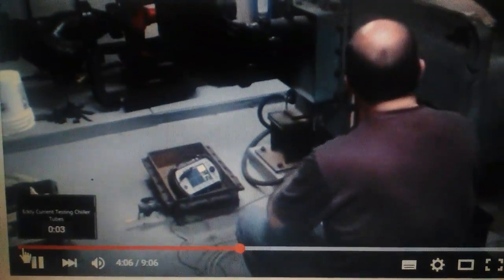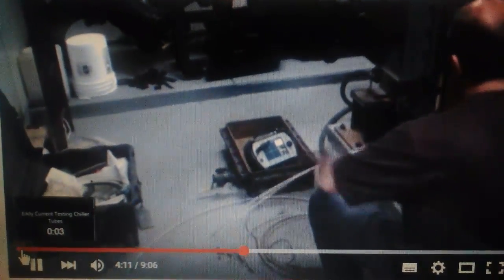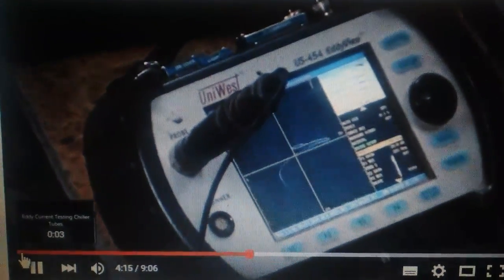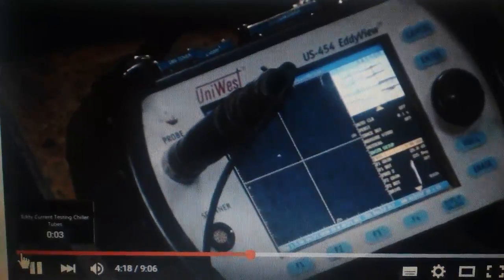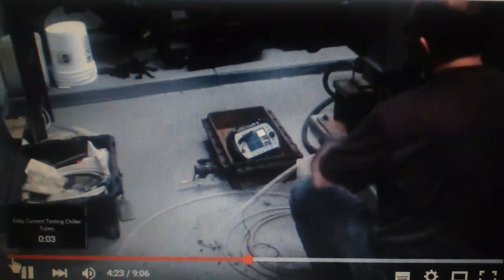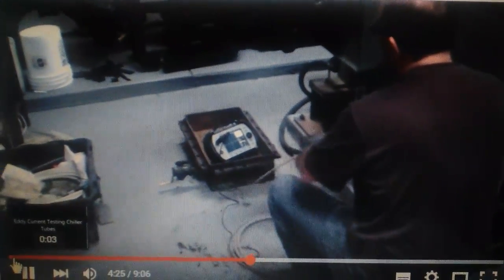Alright, we're doing eddy current testing here on this chiller. There's the eddy current machine right down there on the floor, and you can see the readings that are being displayed there for the technician to see. Here he is taking the eddy current testing rod, putting it down through the tube sheet and into the tubes, through the entire length of the chiller. He's got it marked off so he knows exactly how much distance he needs to go in through the chiller.